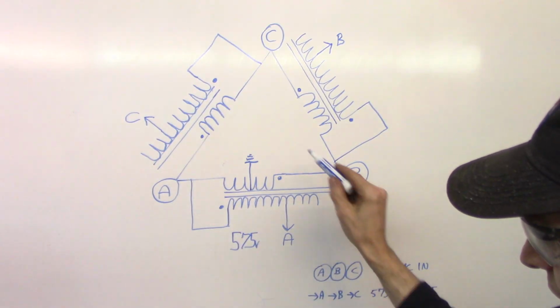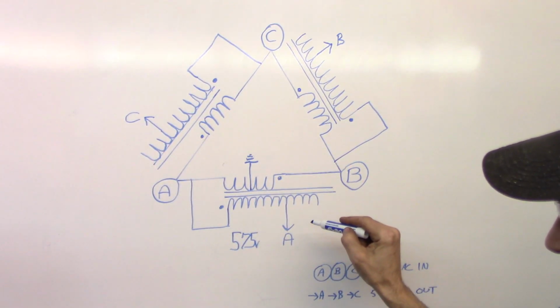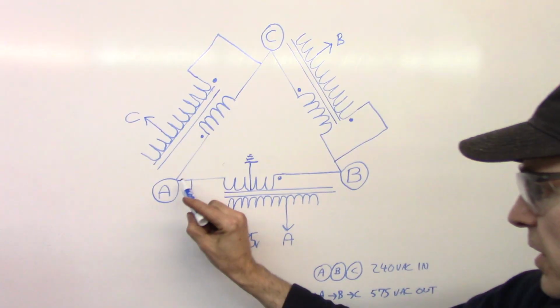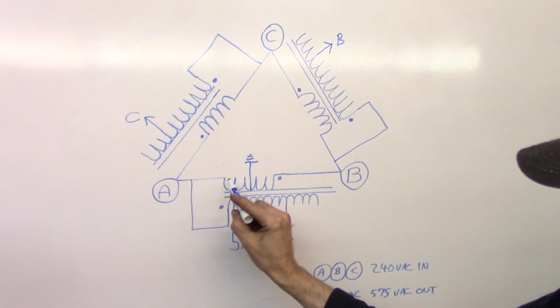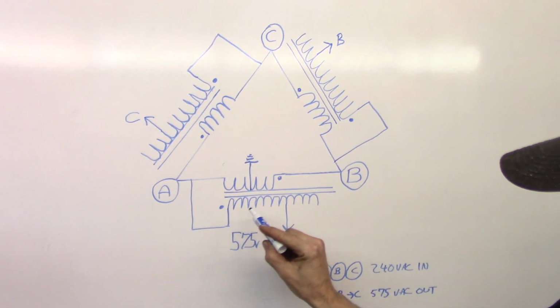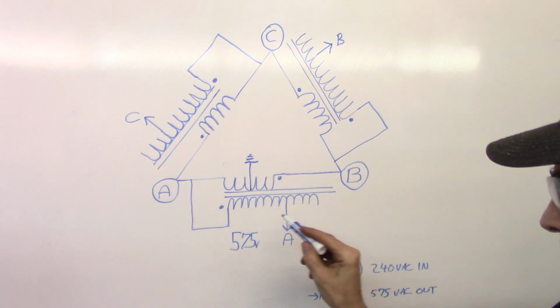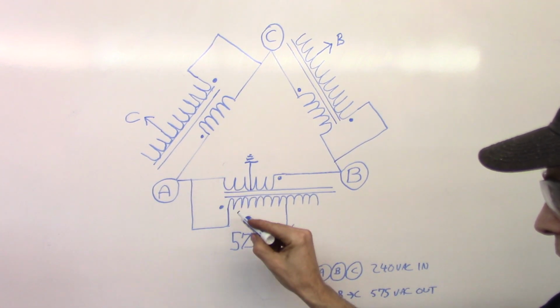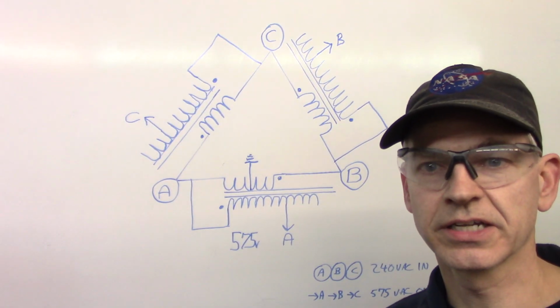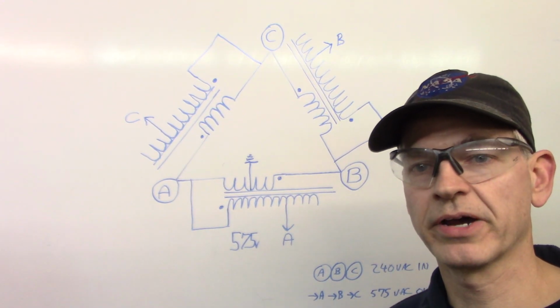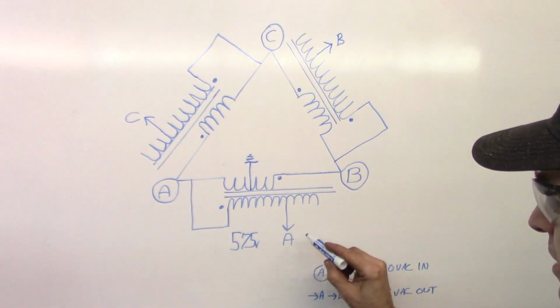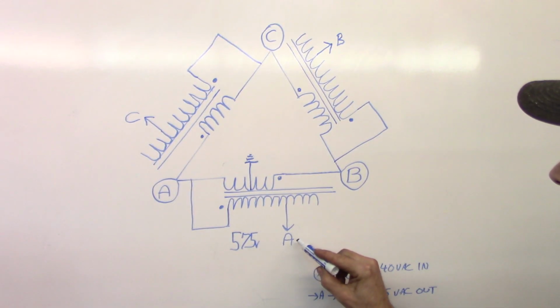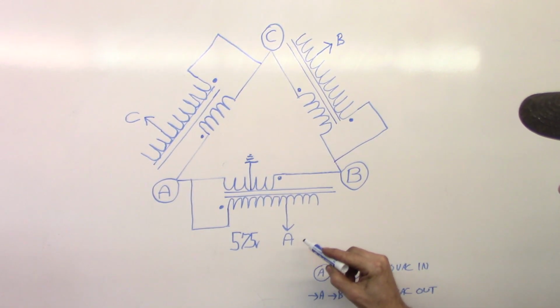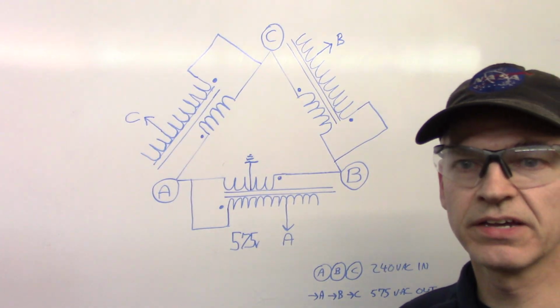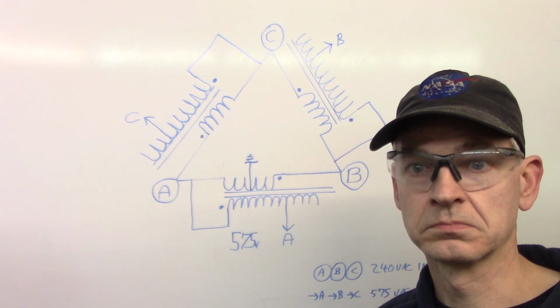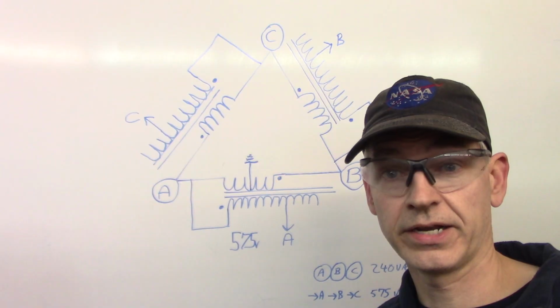Because this is not an isolation transformer—I mean it was, but because this jumper leg jumps the primary to the secondary, or vice versa, jumping one coil to the next, it's no longer isolated. It's not a separately derived power supply. So any of these high voltage legs, output B or output C, if they short to ground, it's going to blow the breaker.